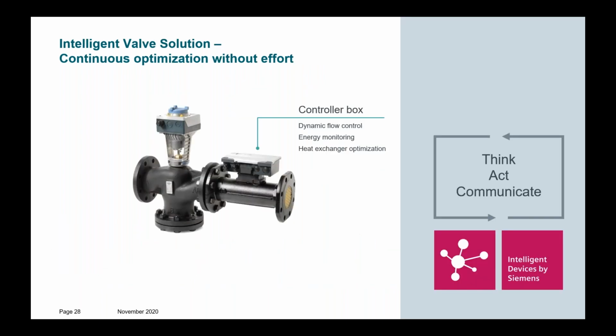Now let's focus on the optimization functions of such intelligent valve solutions a bit more in detail. Why is DeltaT important? Because DeltaT, and especially the return temperature, influences the efficiency of the chiller. With each Kelvin of return temperature you can increase, you will gain at least 3–4% of chiller efficiency. And at the same time, when you increase the DeltaT, you will clearly reduce pumping cost because you reduce flow by a couple of percent.